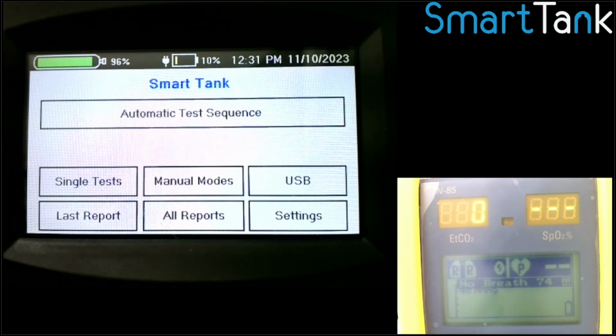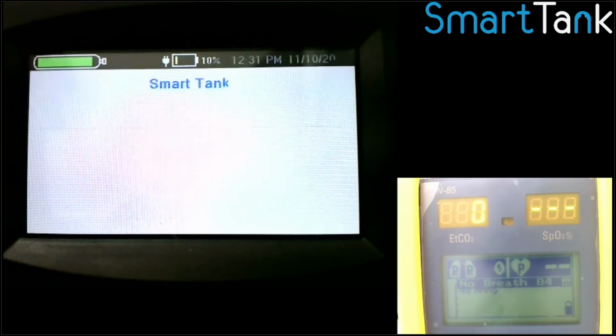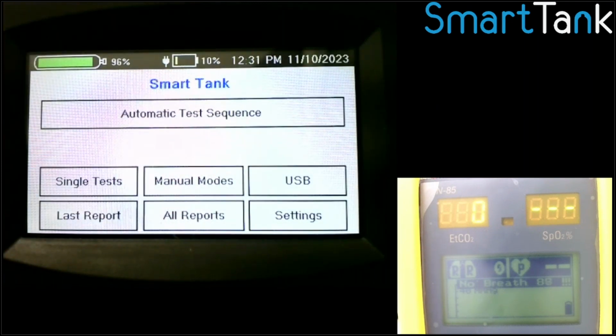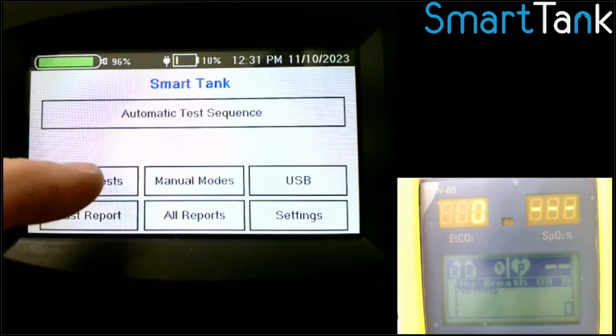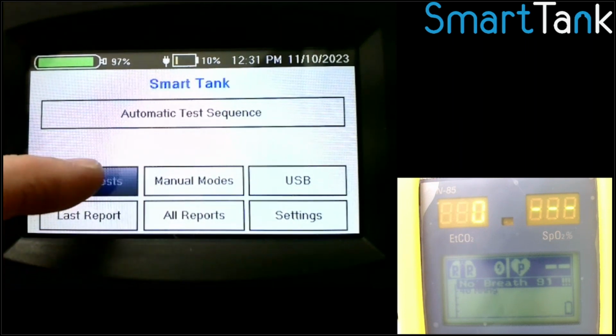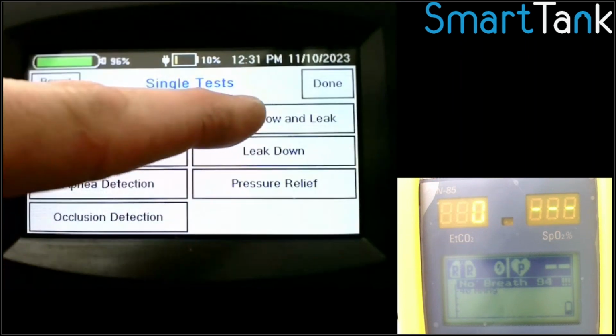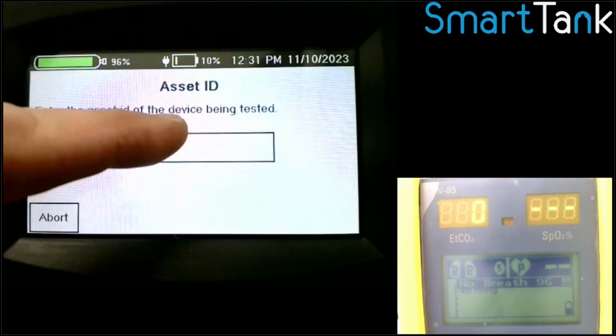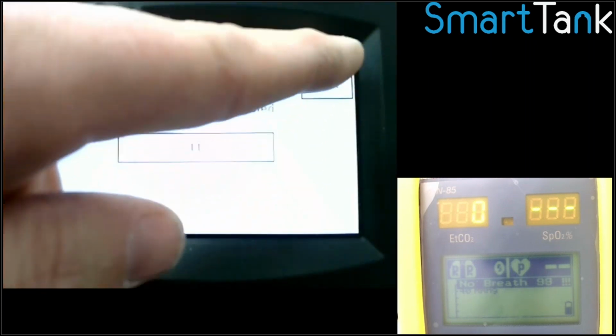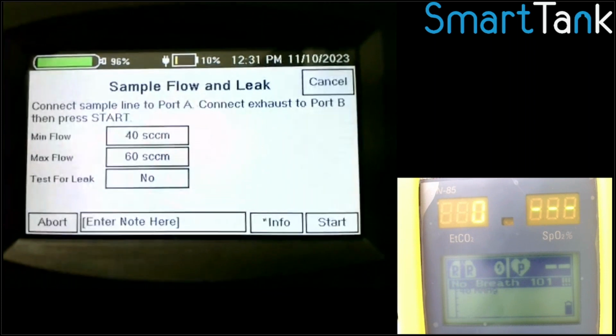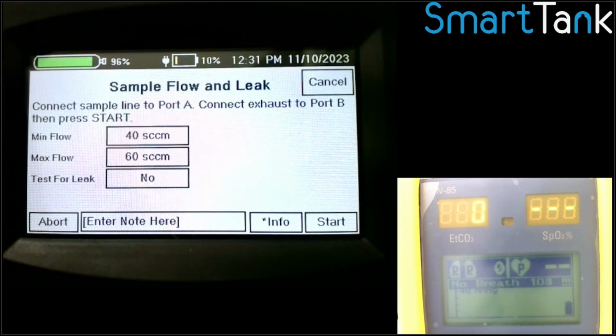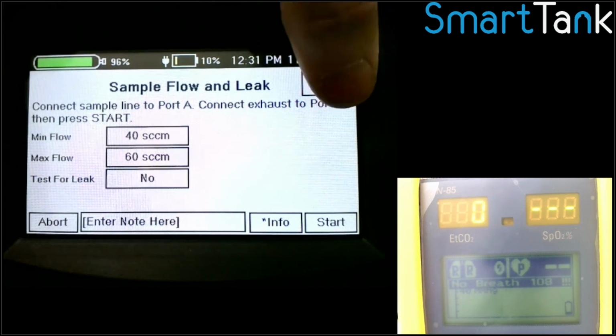So at this point, I'm done. You can then do another PM on a different device. Just walk over and start. Like if you're doing a whole series of them, it remembers the last one you did. Or let's say you're doing some maintenance and you tested something, you can actually come back in through these other options, and let's say you replace the pump, or you did something with the pump. Well, you can go back in and test just the pump using that same flow and leak test procedure, but it's not built into the sequence. It's more of a manual process. And so you could retest something.